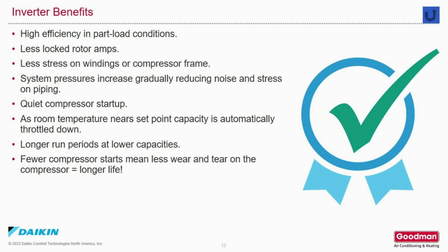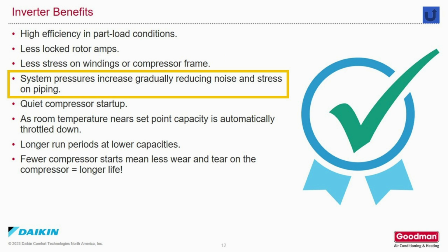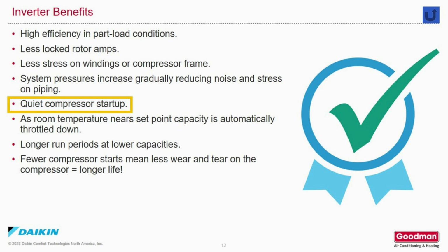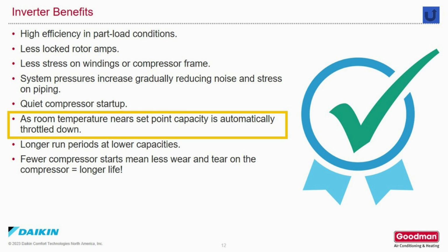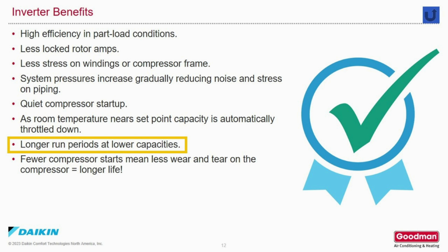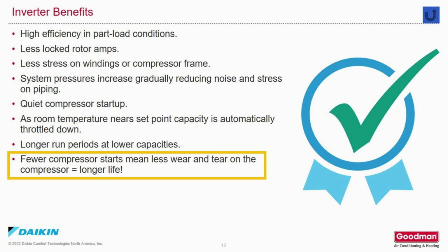Some benefits to an inverter-driven system include high efficiency in part load conditions, less lock rotor amps. The compressor starts at low frequency and increases speed over time, so that eliminates high startup amps. Less stress on the windings or the compressor frame. System pressures increase gradually, reducing noise and stress on piping. Quiet compressor operation. As room temperature nears set point, capacity is reduced rather than on and off cycling, so you get longer run times at lower capacities, increased comfort, and better dehumidification in cooling mode. Fewer compressor starts means less wear and tear on the compressor, which means longer compressor life.